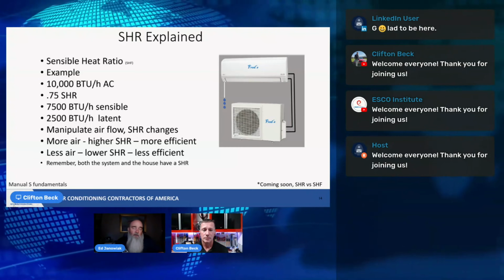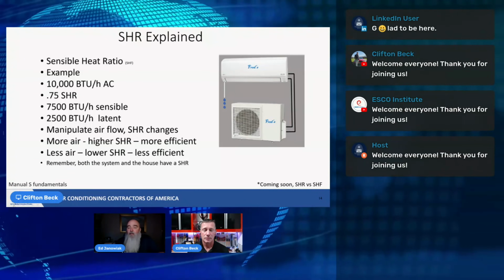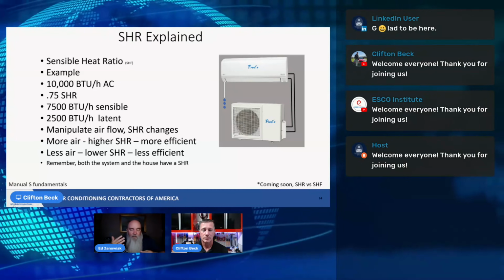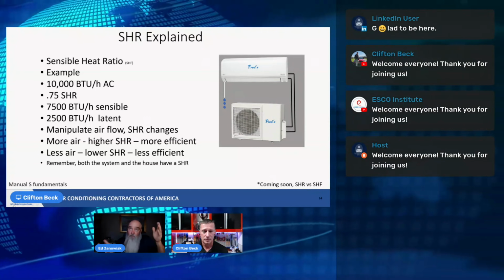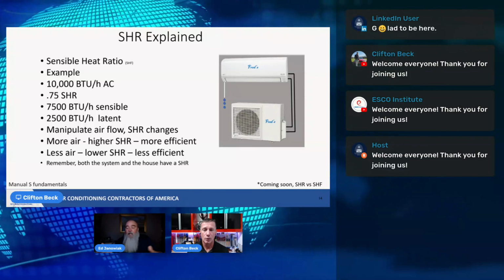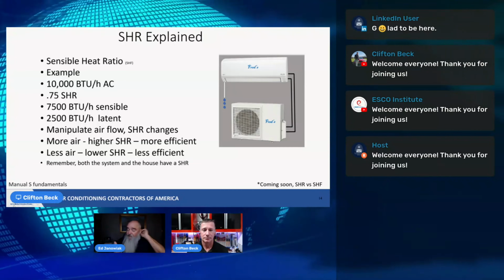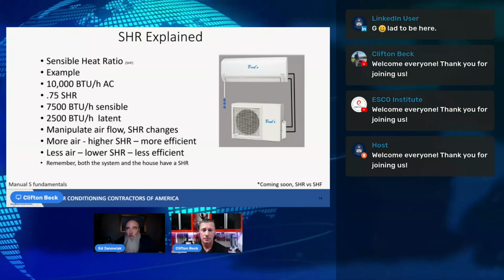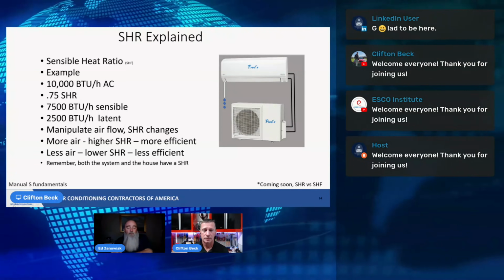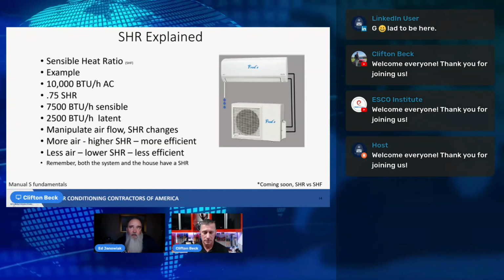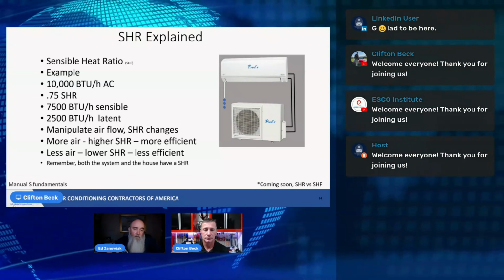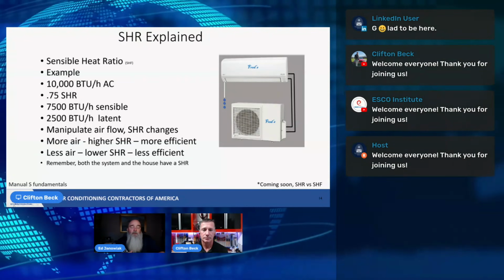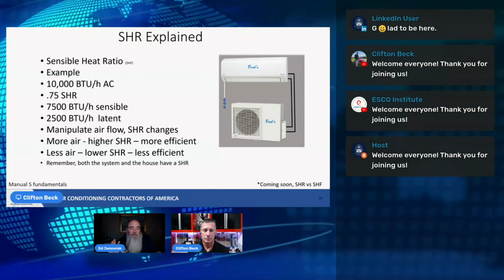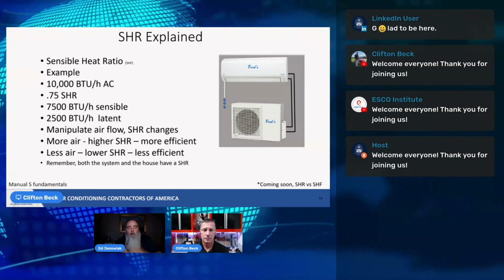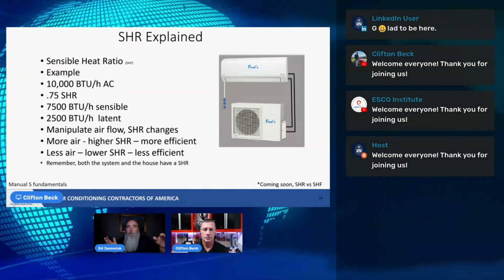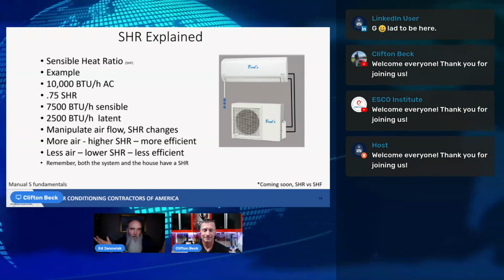Sensible heat ratio is a numerical expression showing how much work our piece of equipment will do per hour, right? BTUH, BTU per hour. Amount of work over time. Yep. And it divvies that up over how much work the equipment's going to do to drop the temperature of the air. And we call those sensible BTUs. And how much work the equipment's going to do to take the evaporator coil down below dew point and get water to condense on it and then run out the white pipe. I mean, that's ultimately what we want to have happen.